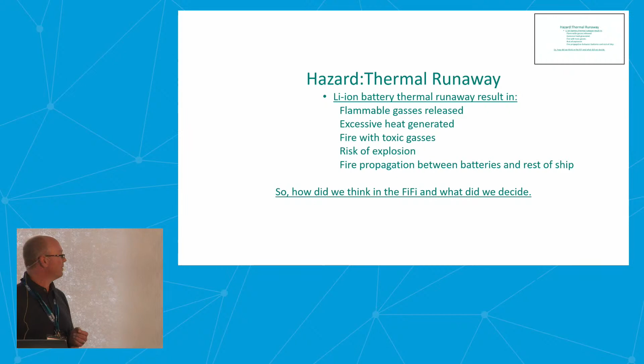So how did we think in the fire safety, and how did we build it? We have, together with the flag state and class, many different things installed. We have the gas detectors in each container, so they are always measuring. And also we have indication outside the containers for the ventilation fans. You're not allowed to go inside the container if it's not indicating the air flow. And these indicators are also connected with the integrated automation system, so you will get an alarm if one of the fans stops.